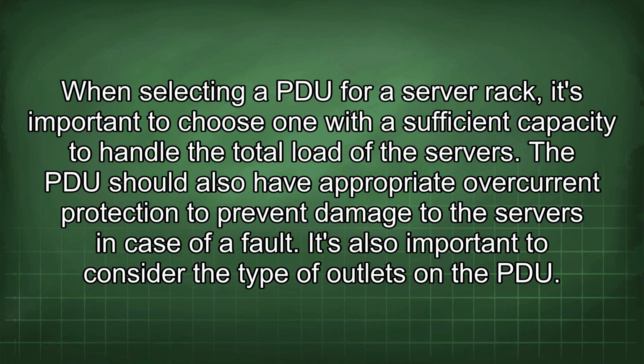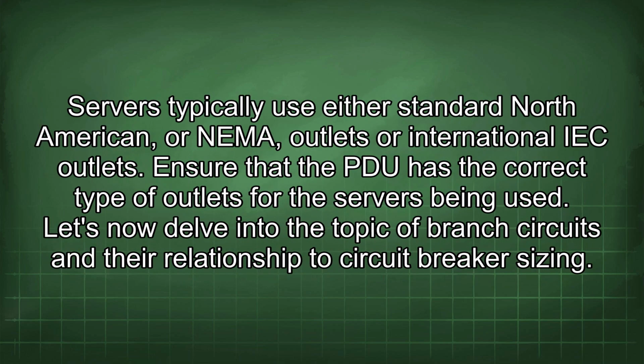It's also important to consider the type of outlets on the PDU. Servers typically use either standard North American NEMA outlets or international IEC outlets. Ensure that the PDU has the correct type of outlets for the servers being used.